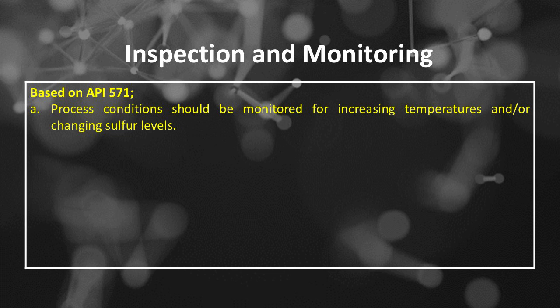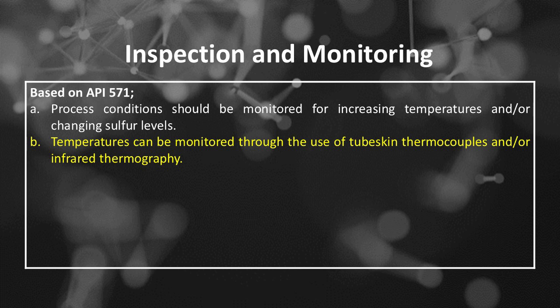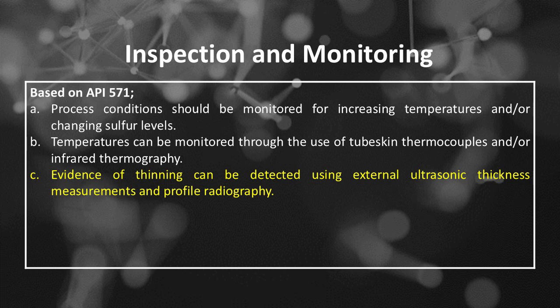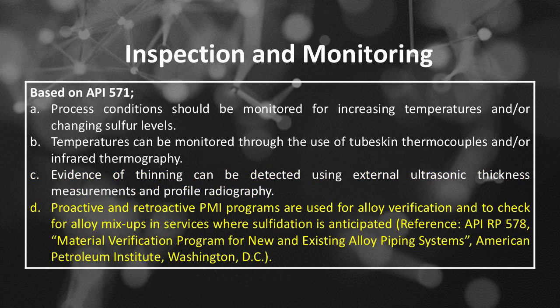Sulfidation damage inspection and monitoring based on API 571: A, process conditions should be monitored for increasing temperatures and/or changing sulfur levels. B, temperatures can be monitored through the use of tube skin thermocouples and/or infrared thermography. C, evidence of thinning can be detected using external ultrasonic thickness measurements and profile radiography. D, proactive and retroactive PMI programs are used for alloy verification and to check for alloy mix-ups in services where sulfidation is anticipated. Reference: API RP 578, Material Verification Program for New and Existing Alloy Piping Systems, American Petroleum Institute, Washington, D.C.